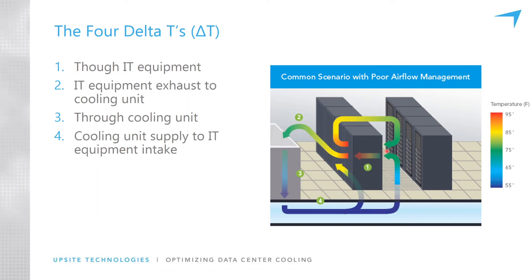One of the most misunderstood concepts in the industry is that you can put all the containment in you want and you are not going to reduce delta T2 unless you reduce fan speeds through the cooling units. If there are only four units of air moving through all the IT equipment but you've got 20 or 30 units of air moving through your cooling units, that extra air is going to find its way back to the cooling unit somehow — it has to — and it's going to mix and reduce that return temperature. So you put containment in place, then you can reduce fan speeds and optimize the room.